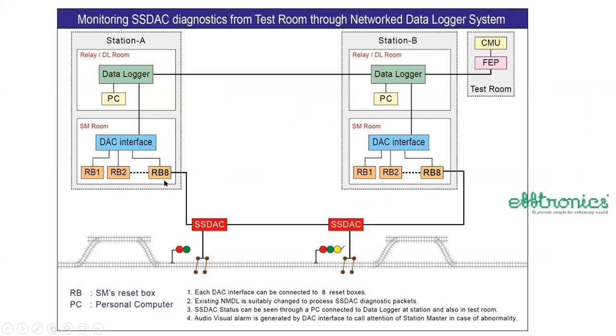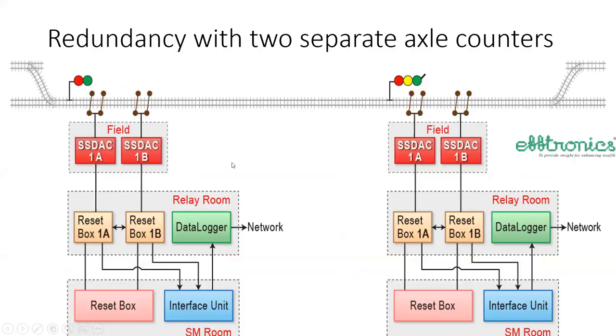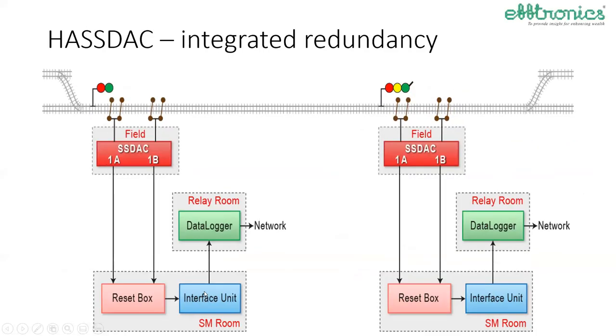At any station, you can have 7, 8 reset boxes because in a junction station there are 3, 4 lines. So you cannot have different interfaces to collect data for each equipment. Up to 8 equipments, one interface is sufficient to collect the data that is given to the station data logger and it reaches the central place. So this is how these interface units are connected, just like this.